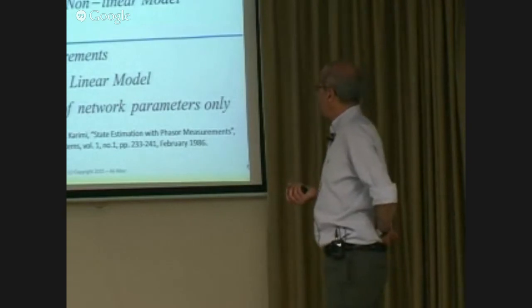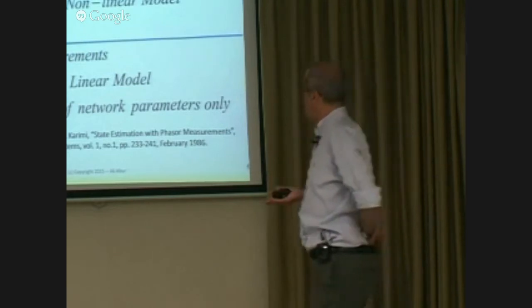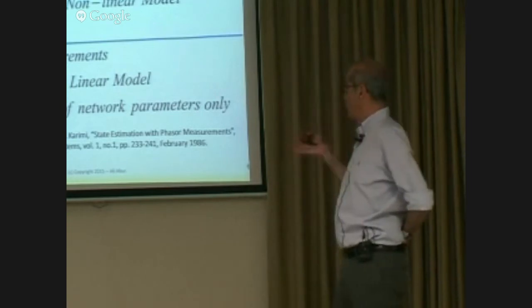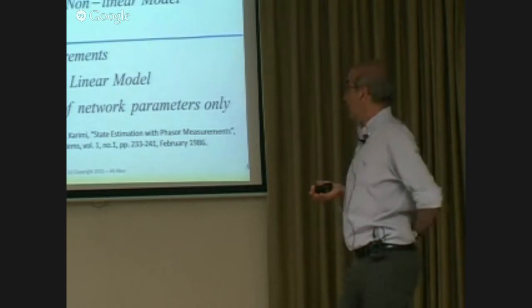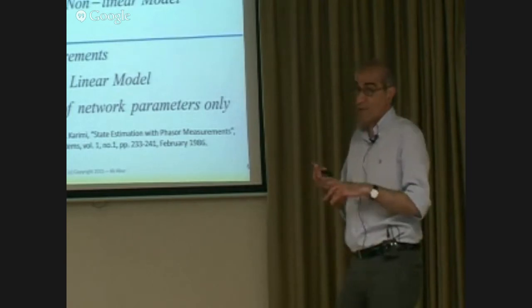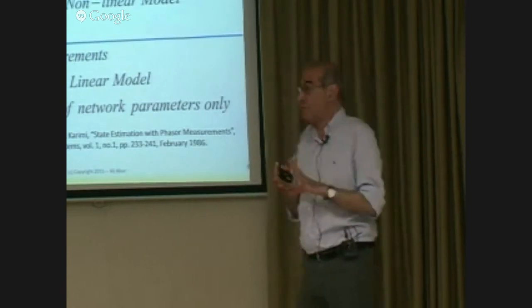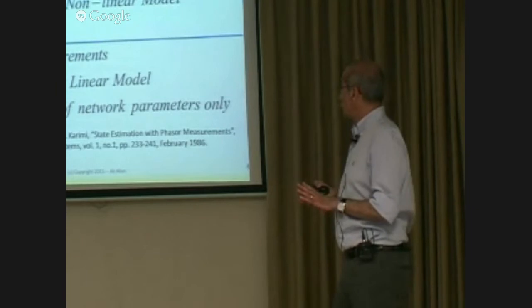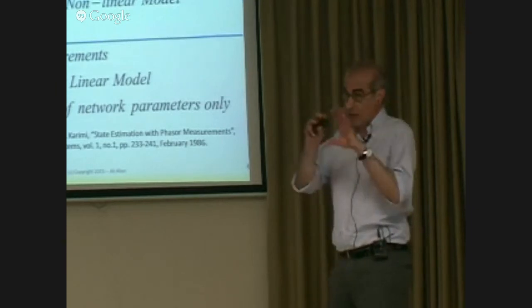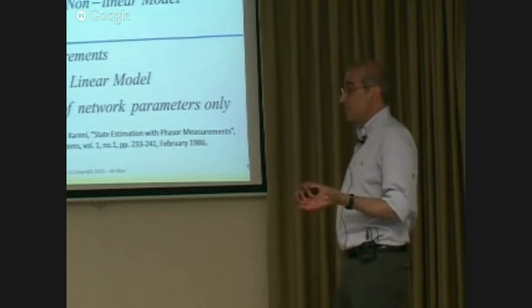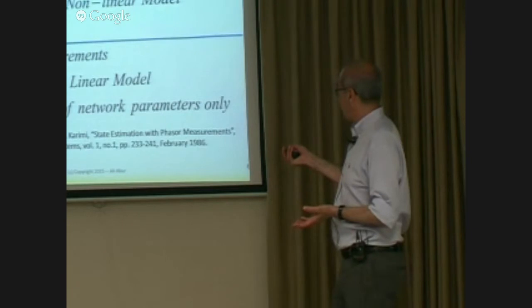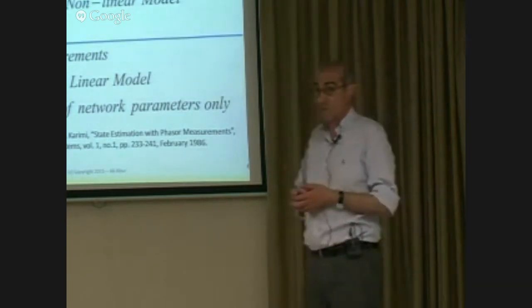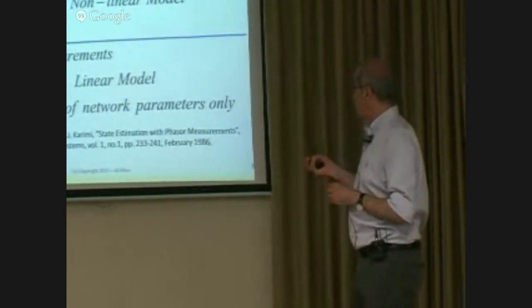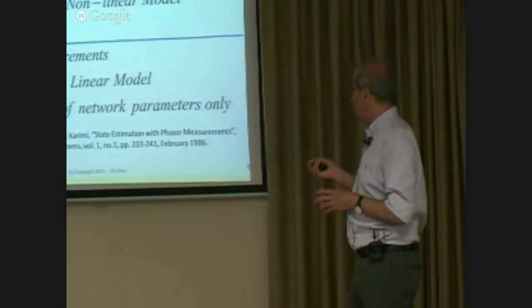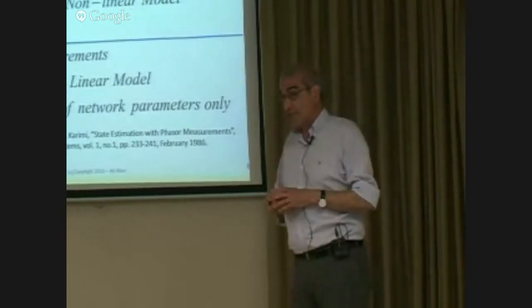So these measurements come in, and in the old days when we did not have PMU measurements, we strictly relied on SCADA. SCADA stands for Supervisory Control and Data Acquisition. Essentially that set includes power flows, power injections, both real and reactive, and voltage magnitude and current magnitude measurements. If you write out the equations for these measurements, they are nonlinear. If you consider X to be your state, basically the voltages at individual buses, and Z denoting those measurements, then those individual measurements will be a nonlinear function of the state.